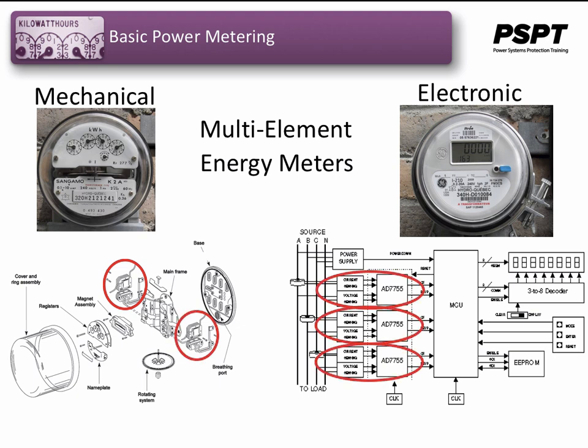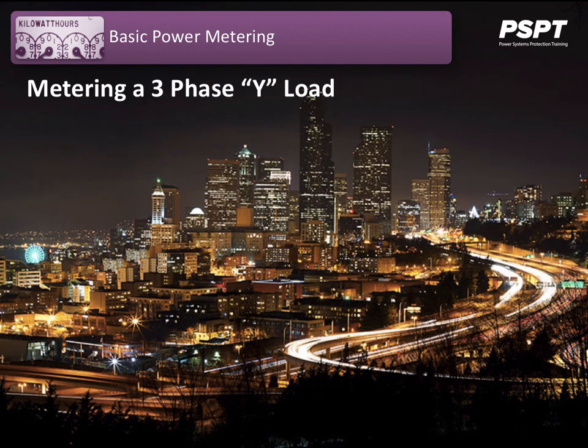Multi-element meters, regardless of whether they are mechanical or electronic, can be made up of two or three elements. Each element reads the average power, which is the RMS voltage times the RMS current times the cosine of the angle between them, which are then summed to give the arithmetic total reading of all of the elements. Let's look at a three-phase Y-connected load.